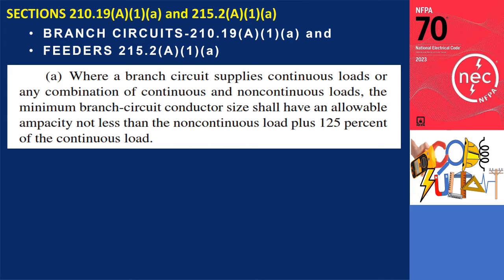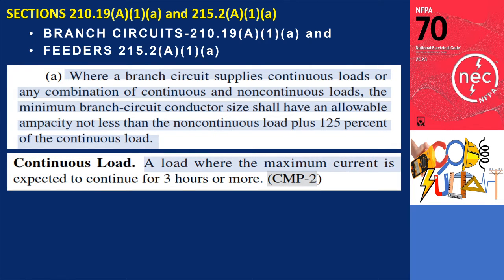Let's start with the basic rules for sizing branch circuits or feeder conductors. Sections 210.19A1A and 215.2A1A have the same language and state that where a branch circuit and feeder supply continuous loads or any combination of continuous and non-continuous loads, the minimum branch circuit or feeder conductor size shall have an ampacity not less than the non-continuous load plus 125% of the continuous load. The code defines a continuous load as one where the maximum current is expected to continue for 3 hours or more.